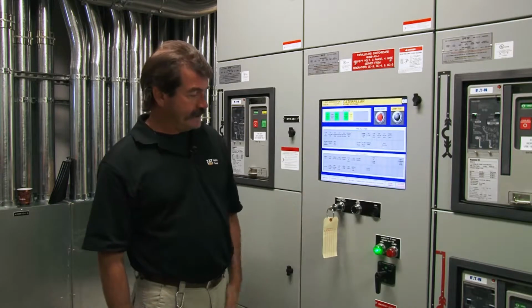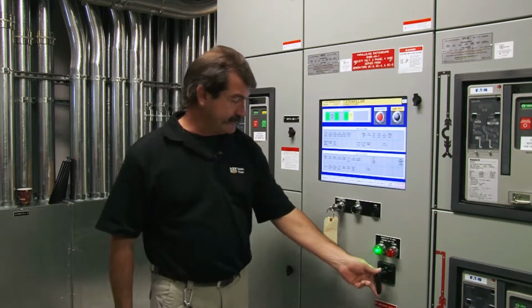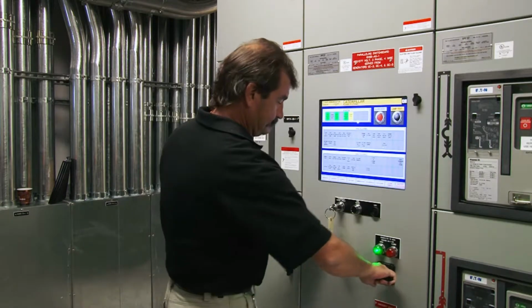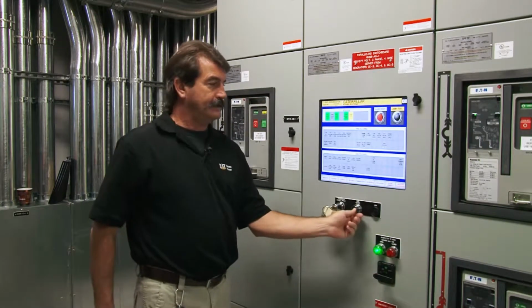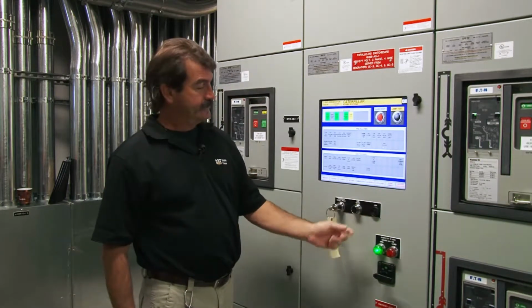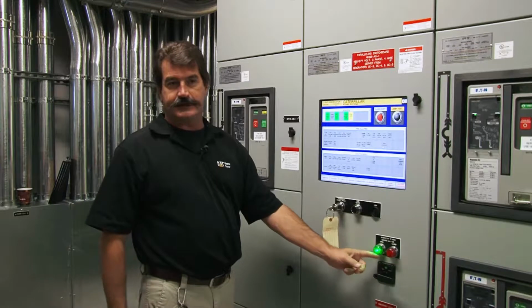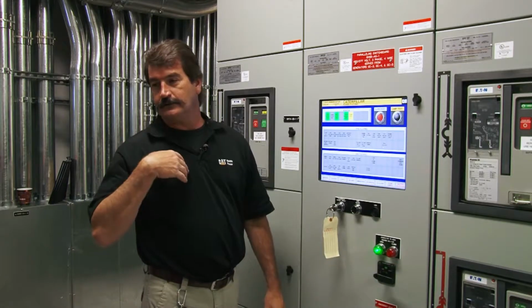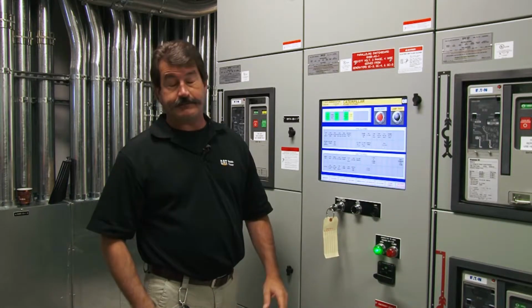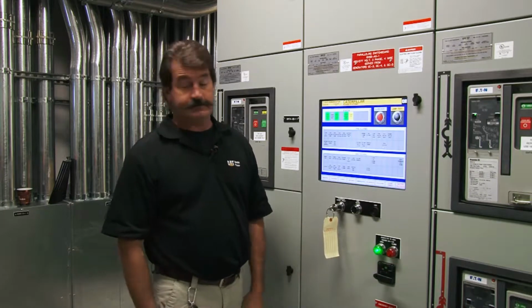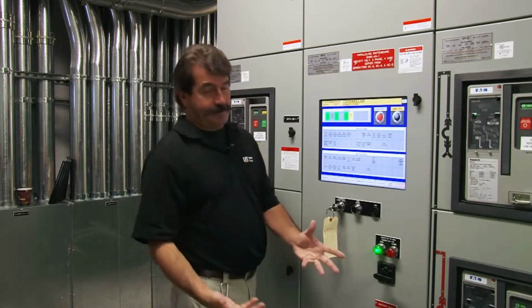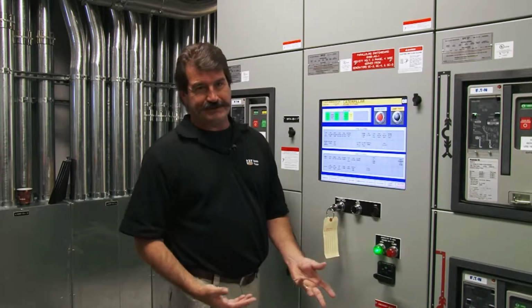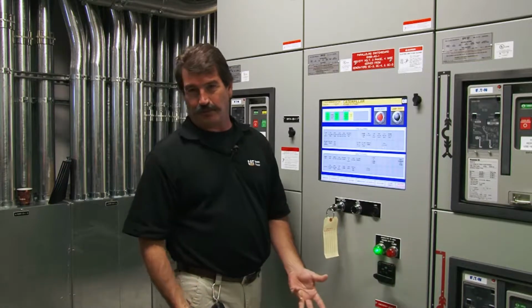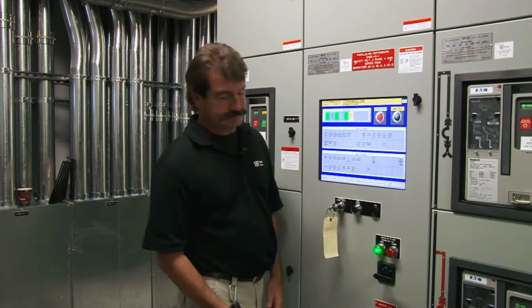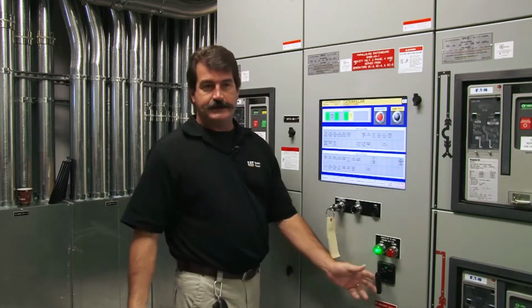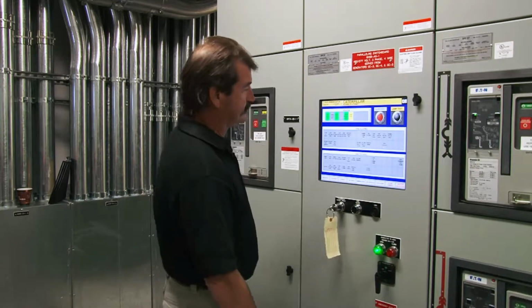And then pull to lock right here, all that does is keep that breaker from shutting automatically. So don't think of it as a safety function. If you have to worry about safety, rack out the breaker. And to get it back, just hit it and it'll spring back into position right there.